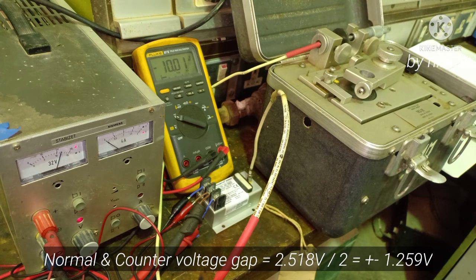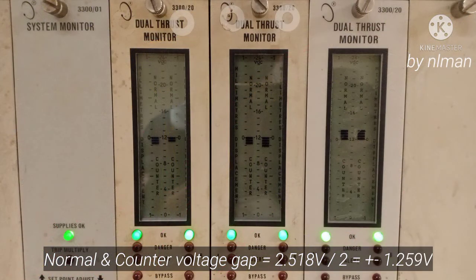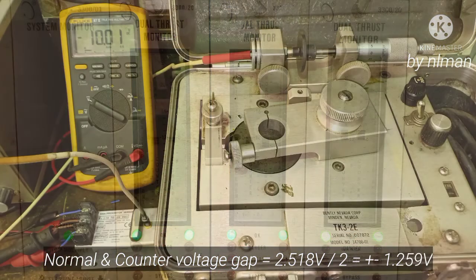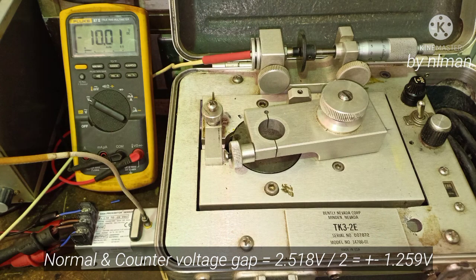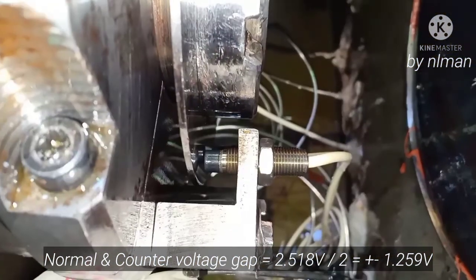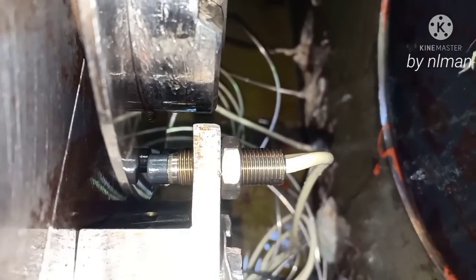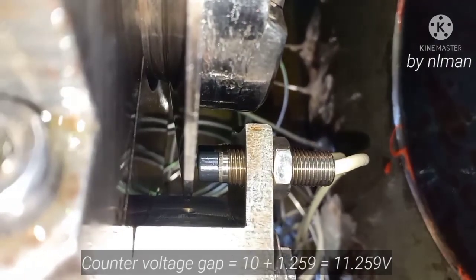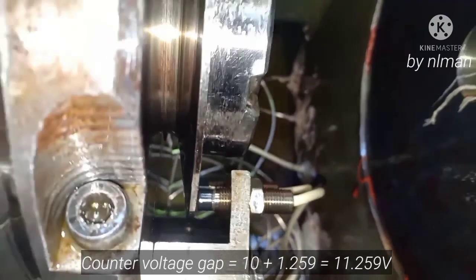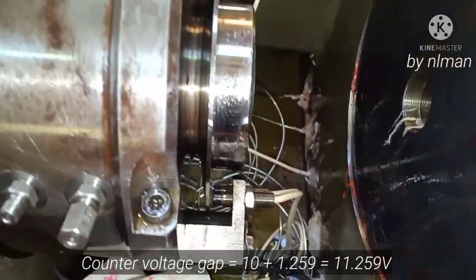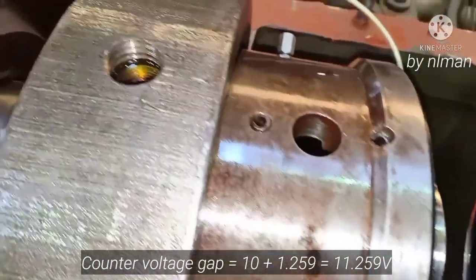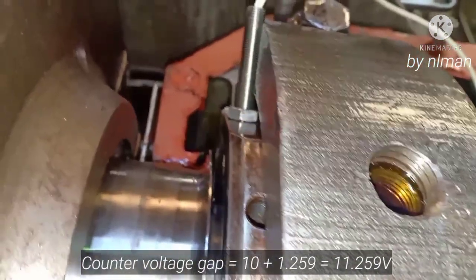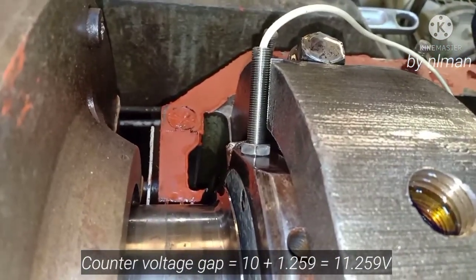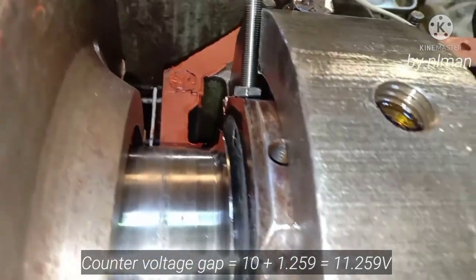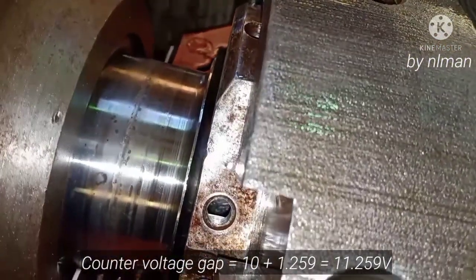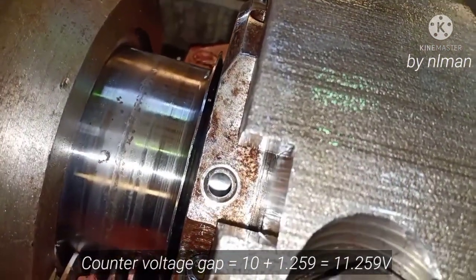so our value now is 2.518 volts. You divide it by 2, so we can get for the normal and counter plus minus 1.259 volts. Okay, so to get our counter voltage, because the given for the center is 10 volts, the counter voltage gap will be 10 plus 1.259 volts, so the equivalent of 11.259 volts. So that is for our counter voltage gap.